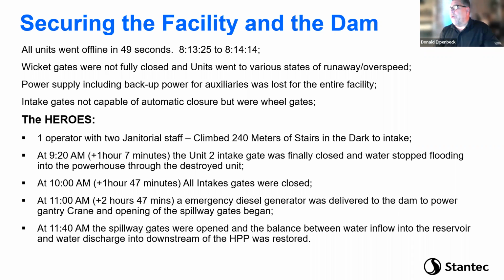That actually was only part of the problem, because then they turned off all the water flowing through the turbines, but the reservoir was fairly full and the water level began to climb in the reservoir, and they didn't have any power to the spillway gates. So they had to get an emergency diesel generator, which took them about another hour to get emergency backup power there so they could begin to open the spillway gates to begin to release water. And so at 11:40, 3 hours and 30 minutes after the event, they were finally able to get the water situation at the dam stabilized and shut off.